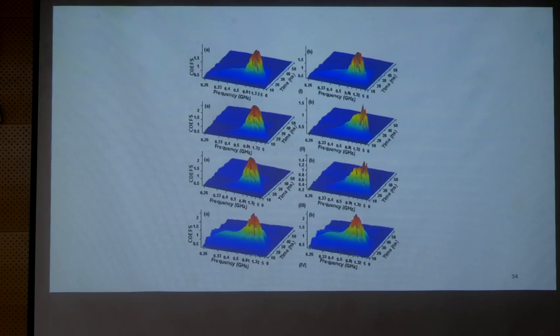Corona will have a different signature, surface discharge will have a different one, and likewise the internal discharge in the insulation will have a different one. In that way you will be able to extract easily what is occurring.